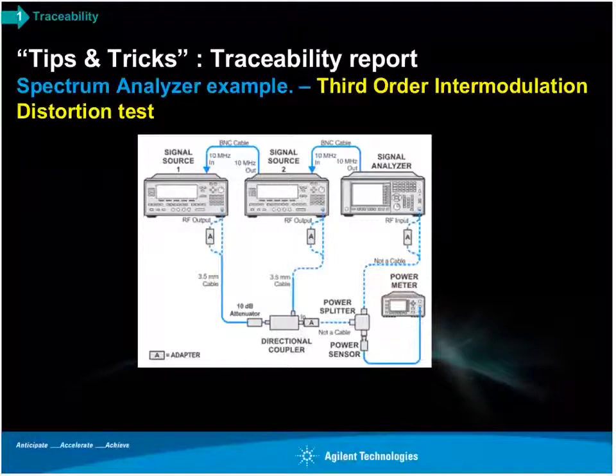Here's one. If you're looking on the traceability report and the instrument that you submitted for calibration, the device under test, is a spectrum analyzer, then one of the tests that is performed is on third-order intermodulation distortion. If you've ever used a spectrum analyzer where you have one signal that's already there, could be a large or small signal, and you're doing a sweep over a frequency range, looking to see whether there is anything there that you didn't expect, then you are relying on third-order intermodulation distortion. I would submit that almost everybody that uses an analyzer depends on this particular specification.